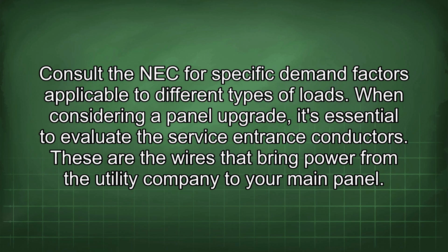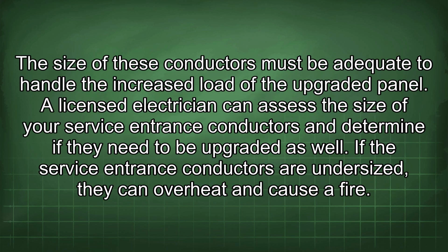When considering a panel upgrade, it's essential to evaluate the service entrance conductors. These are the wires that bring power from the utility company to your main panel. The size of these conductors must be adequate to handle the increased load of the upgraded panel. A licensed electrician can assess the size of your service entrance conductors and determine if they need to be upgraded as well. If the service entrance conductors are undersized, they can overheat and cause a fire.